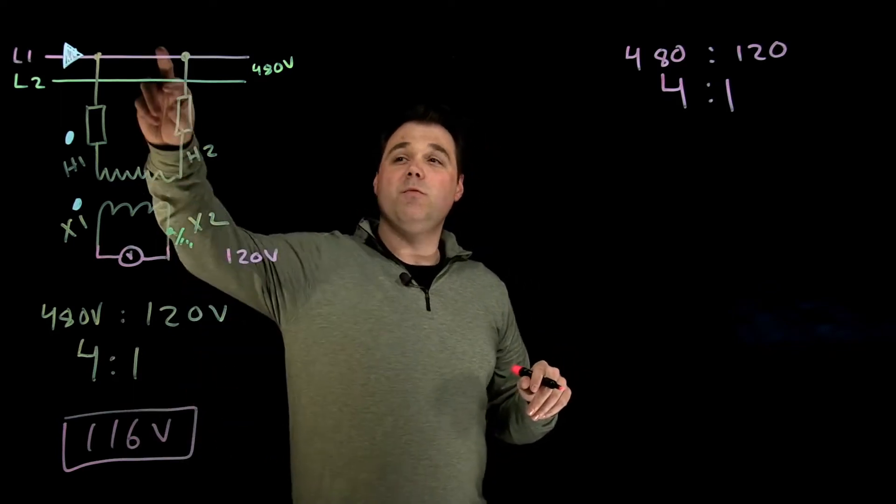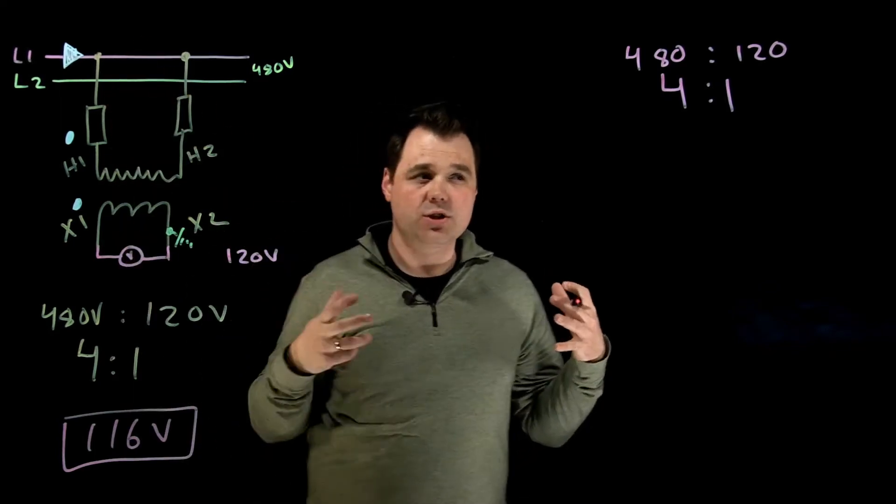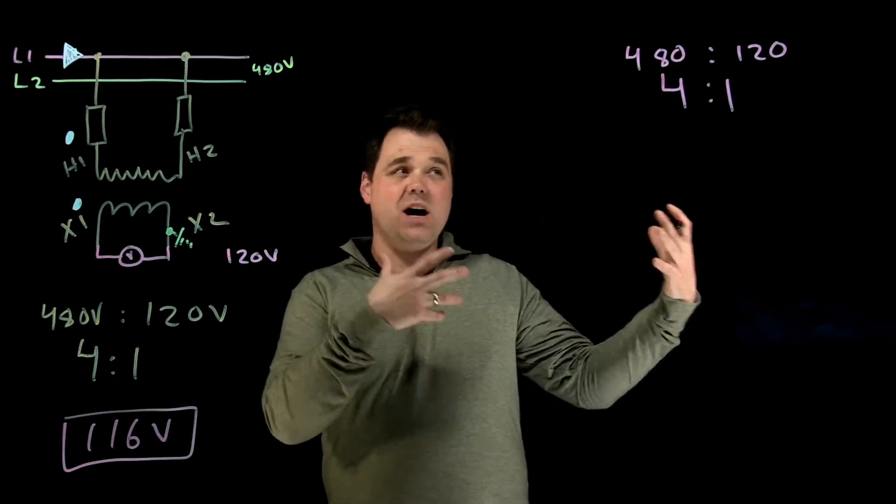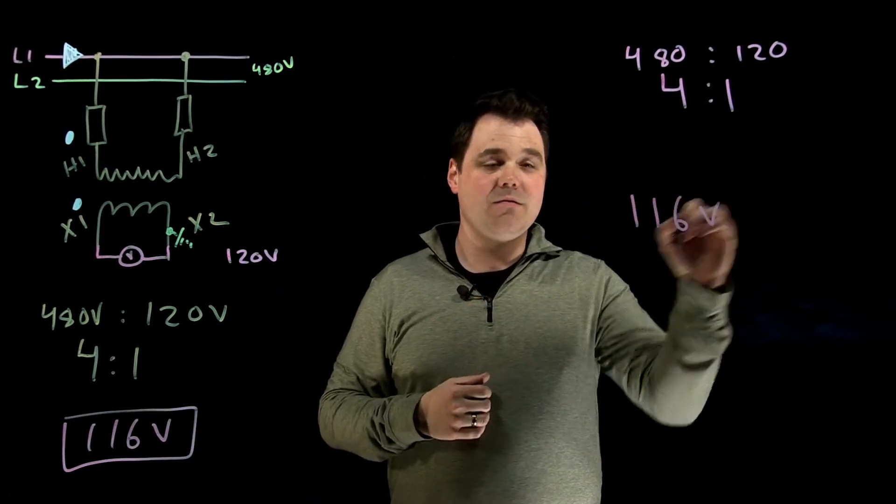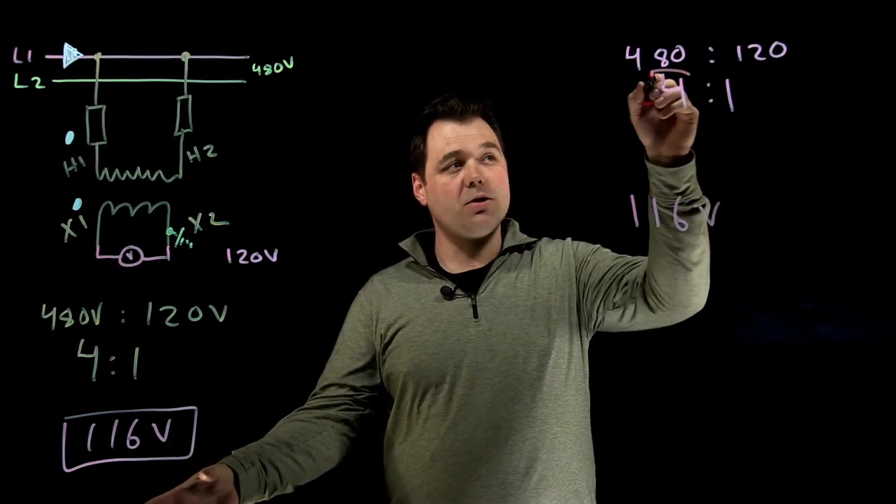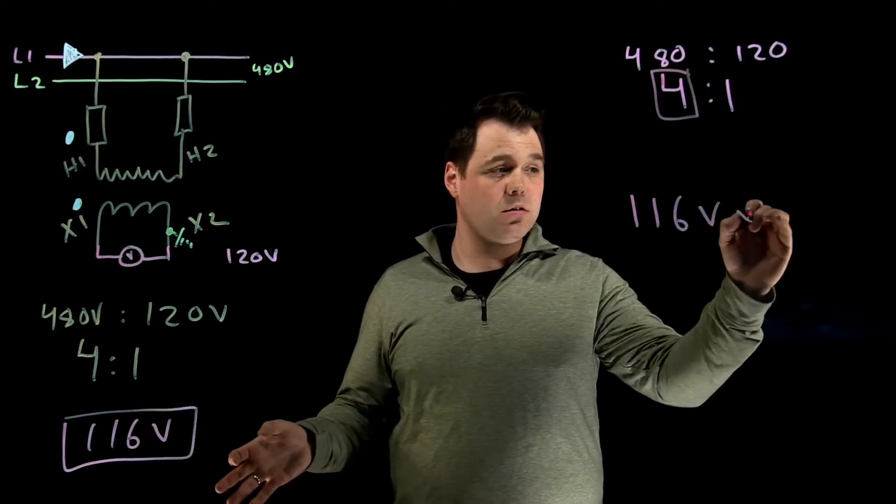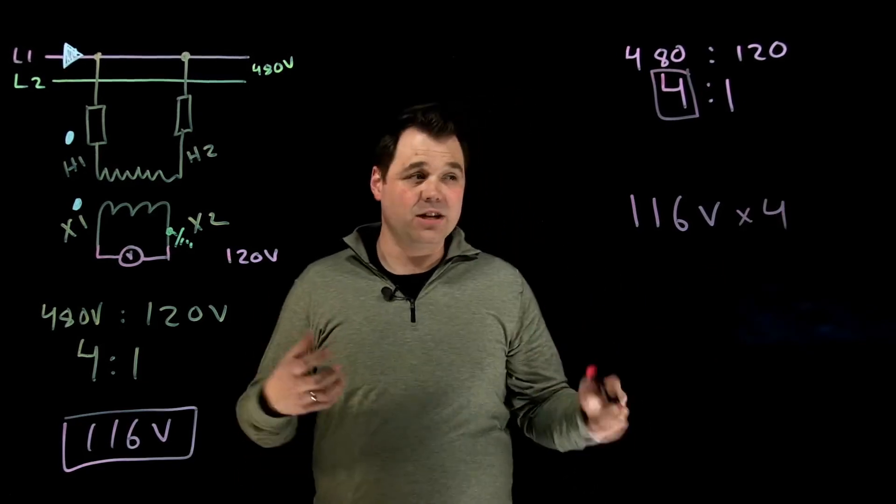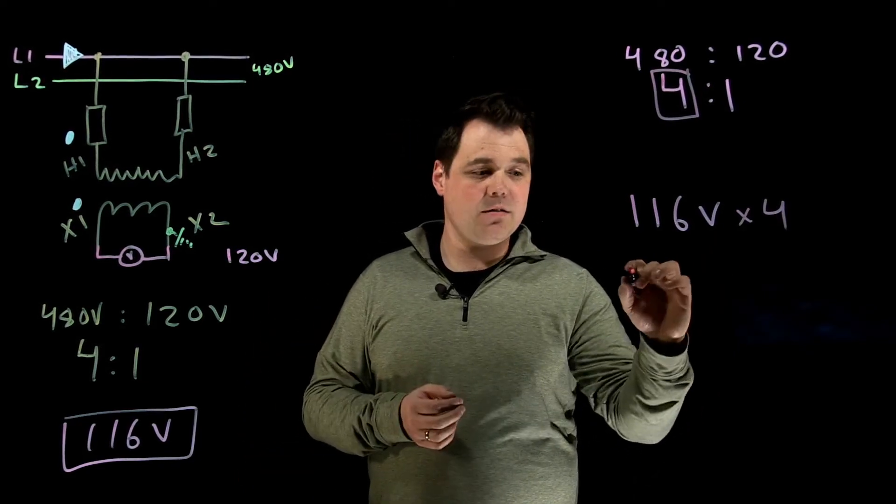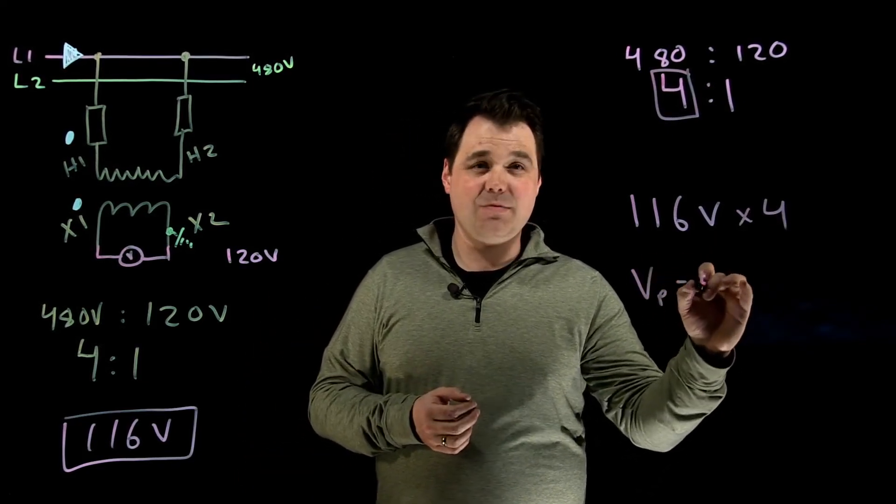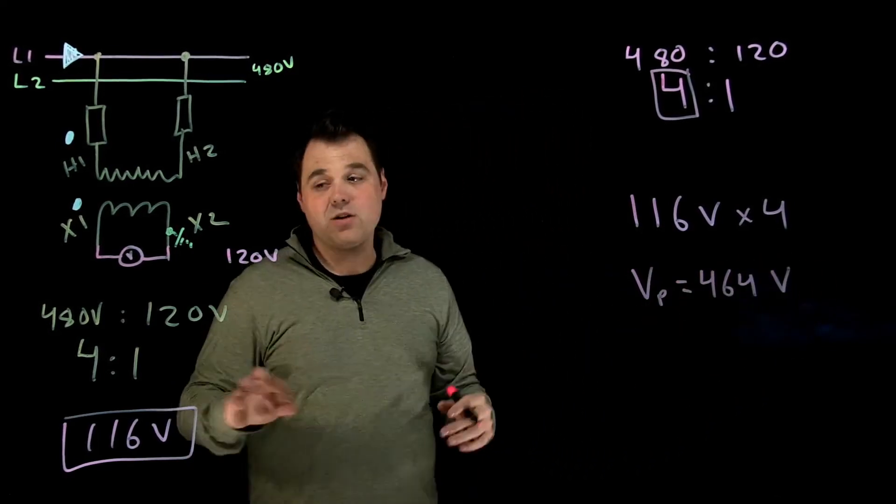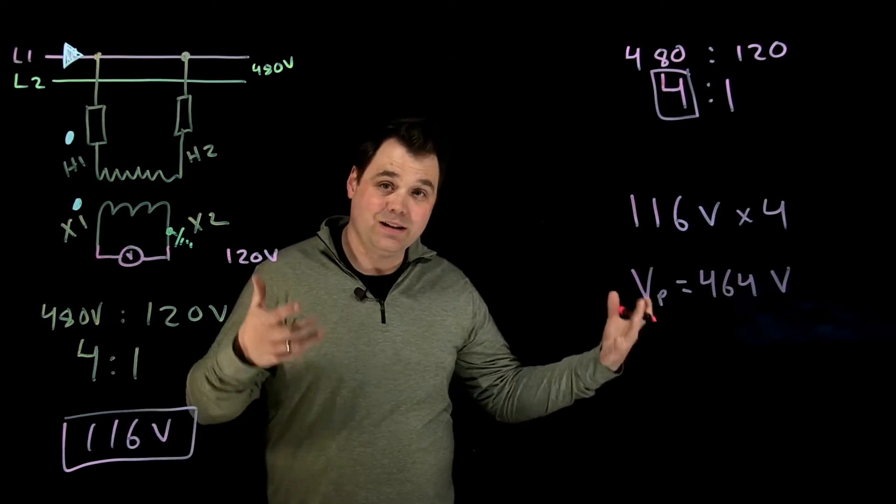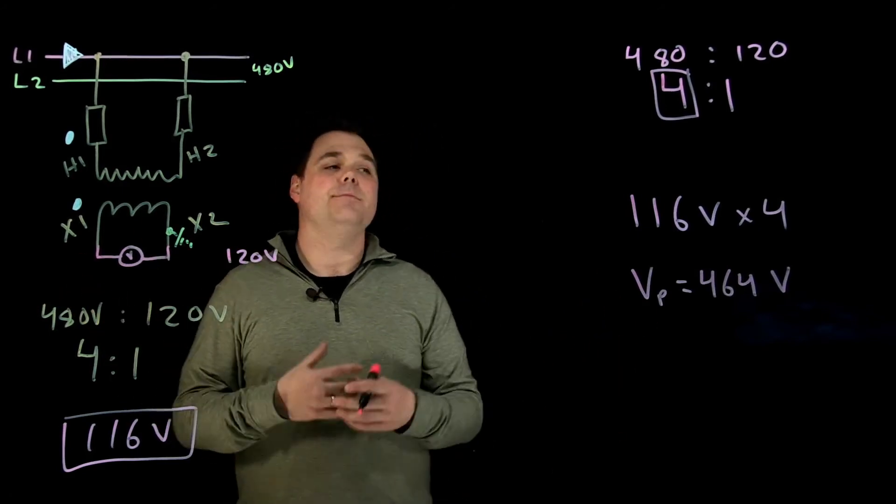What does that mean would be my actual primary voltage? Well, in this case, if we read 116 volts, we're going to take 116 volts that I'm reading, multiply it by my ratio. That tells us that on the primary, it would actually be 464 volts, but our meter only needs to be rated for that 120.